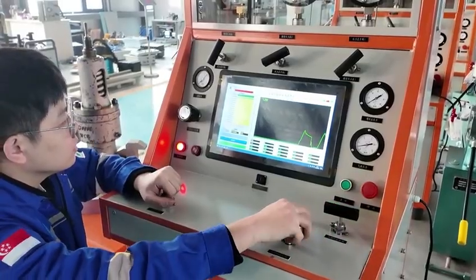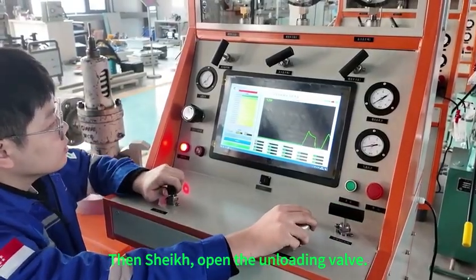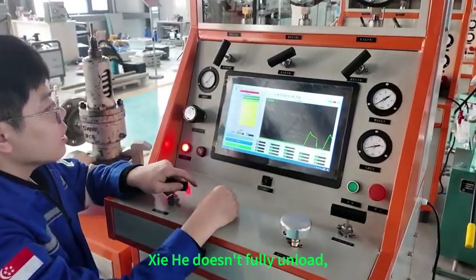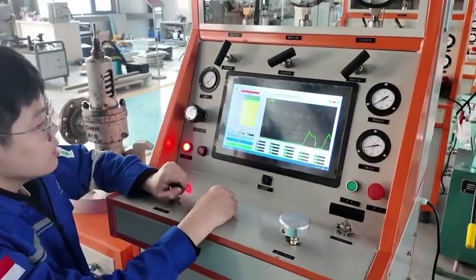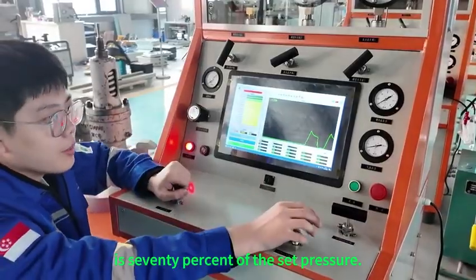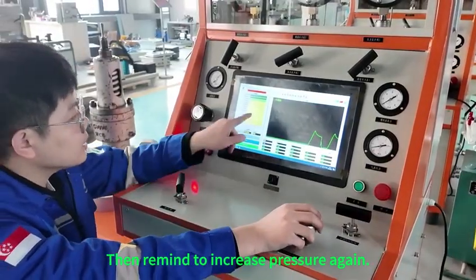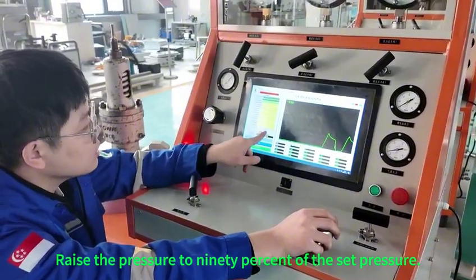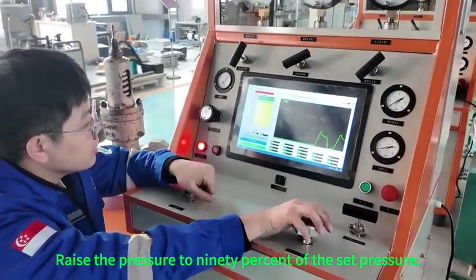Okay. Then open the unloading valve. See, it doesn't fully unload. It's 70% of the set pressure. Then it reminds us to increase the pressure again, to 90% of the set pressure.